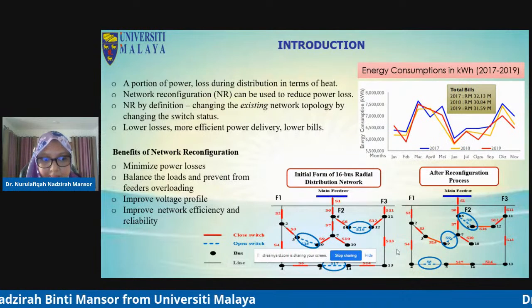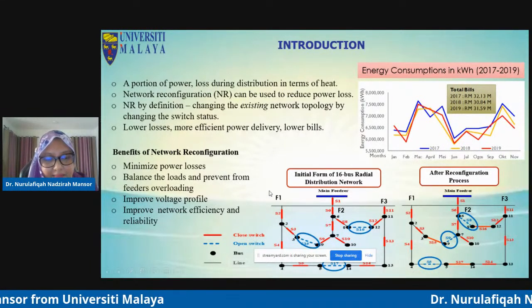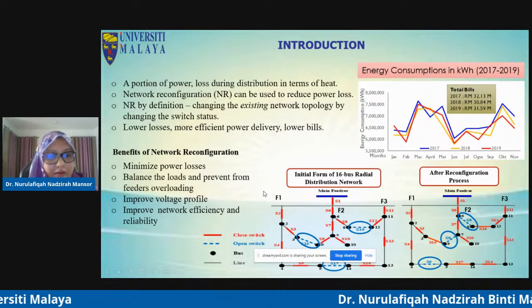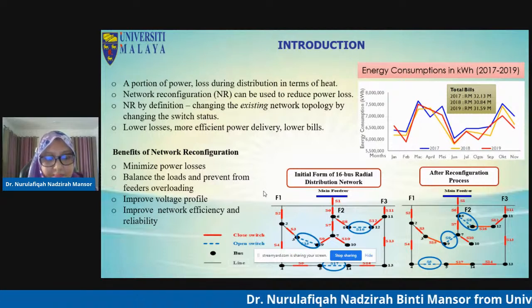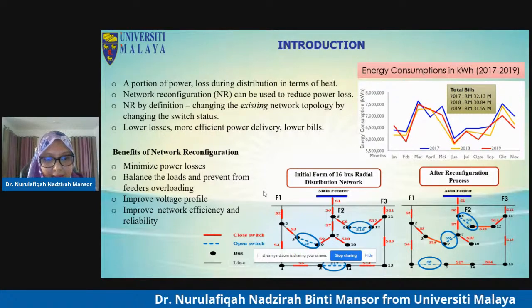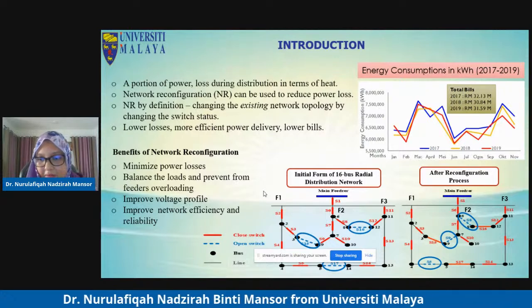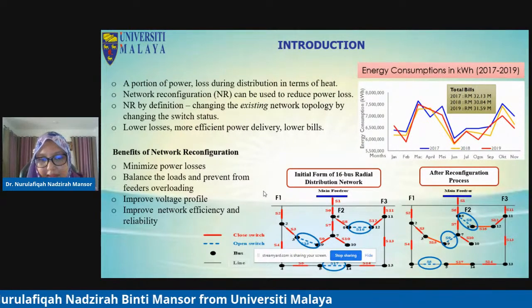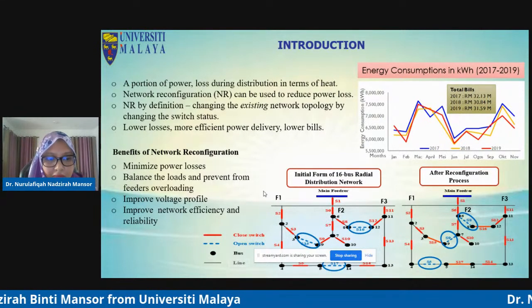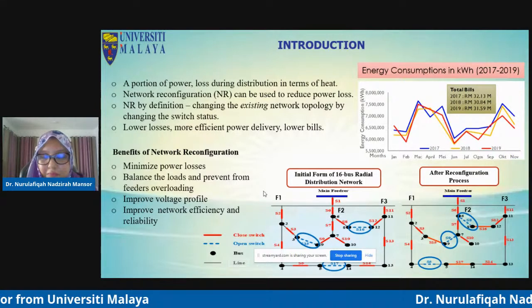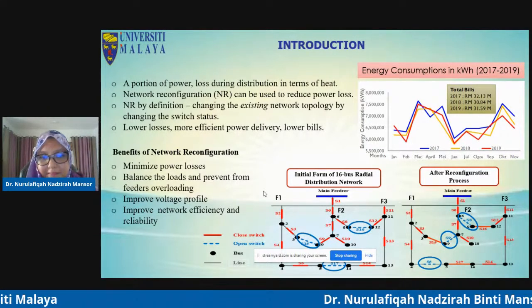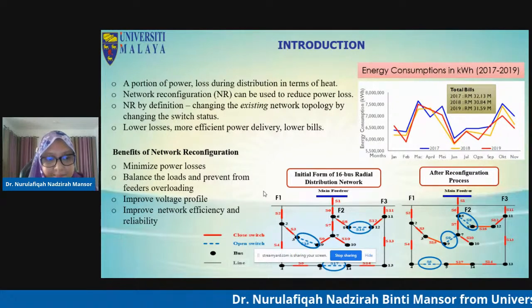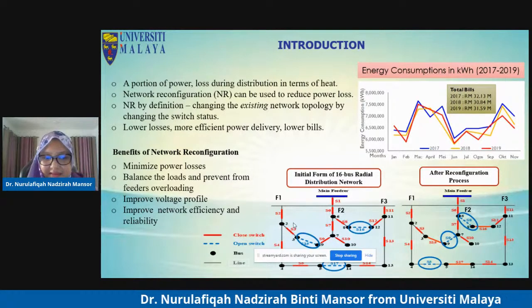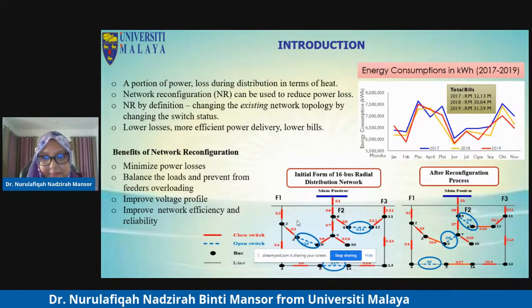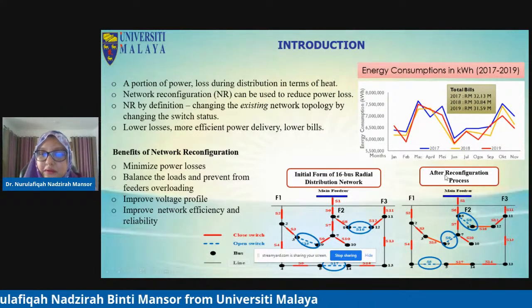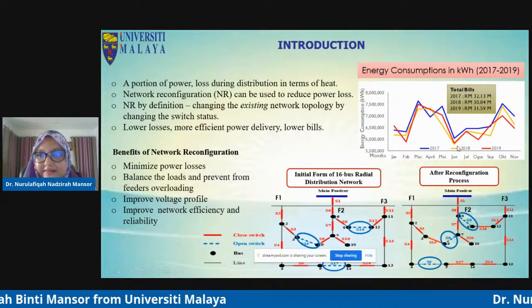Apart from minimizing power losses, network reconfiguration, or NR for short, could help balance the load and prevent feeders from overloading, because we transfer load from one feeder to another. We could also improve the voltage profile, especially on the bus downstream of the feeder, improve network efficiency as well as reliability.